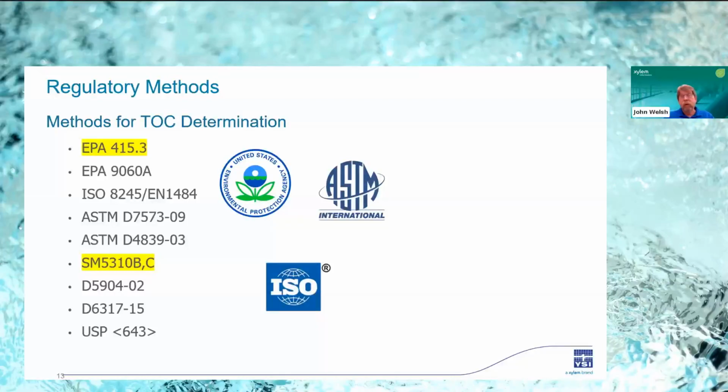And as far as the Model 9220 online TOC goes, that instrument conforms to EPA 415.3 and standard method 5310C. So now let's just take a quick look at and review the components of the Model 9220 and how it performs this measurement.